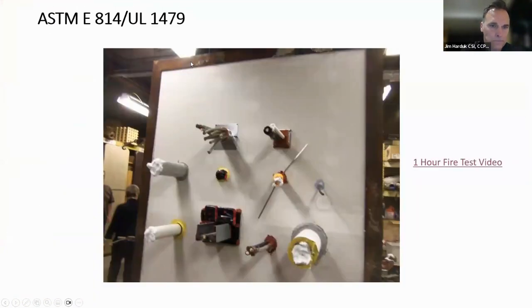So what I'm going to show you here is the ASTM E814. Can you back up, please? The ASTM E814. What we're showing you here is a test that was administered at UL. It's a 1 hour wall assembly, a gypsum wall assembly. And you'll notice on the wall assembly there are several penetrating items. It looks like we have a bundle of cable, some insulated pipe, some plastic pipe, metal conduit. Looks like we also have a cable tray.